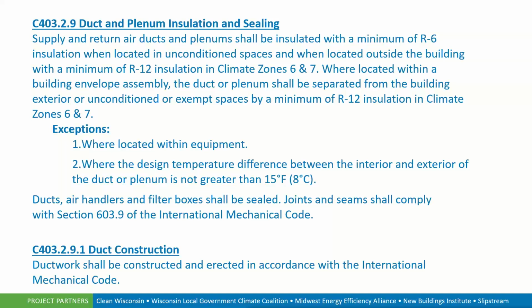Duct and plenum insulation and sealing. It's required that supply and return ducts be insulated to a minimum of R6 when they're located in unconditioned spaces. If those ducts are outside of the building, they need to be a minimum of R12 in climate zone 6 and 7, which is Wisconsin. And when located within the building thermal envelope assembly, that duct or plenum should be separated from the building exterior, unconditioned or exempt spaces by a minimum of R12 in climate zone 6 or 7. So if we have that duct running up an exterior wall, we need to make sure we have that separation where the duct is adjoining an unconditioned attic. We need to have that R12 insulation.